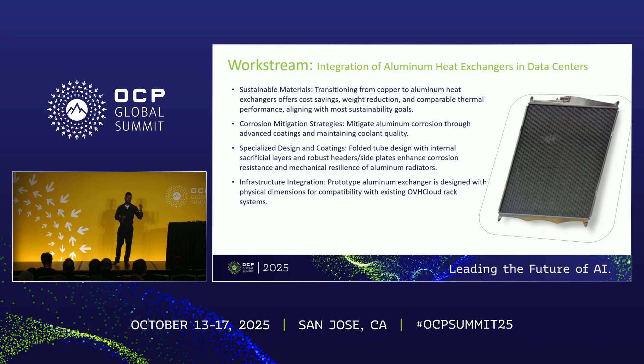We talk about corrosion mitigation strategies and design considerations. We're partnering with Valeo and OVH Cloud — Valeo comes from the automotive industry and their heat exchanger form factors differ from the OCP form factor, and OVH Cloud has its own idiosyncrasies with how they deploy servers and racks. That said, the physics are still the same, the corrosion management is the same, and the performance is the same, so it should apply to any implementation of an aluminum heat exchanger.